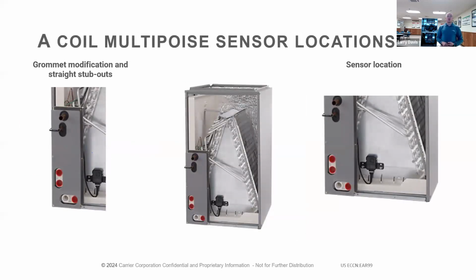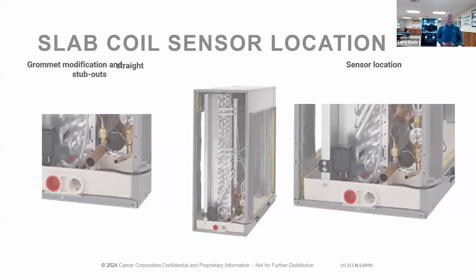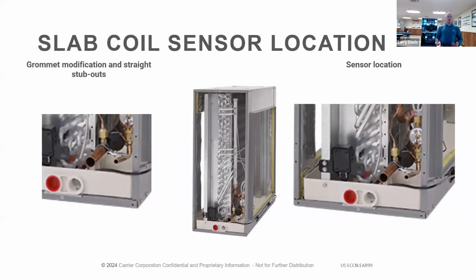Here's the same thing for the A coil. You see that sensor, it's just mounted low. The refrigerant's going to want to accumulate low in the area, so that's where it's going to pick it up. Slab coil, don't know if anybody still uses those, but yeah, there's there. Same thing for the location for the sensor.